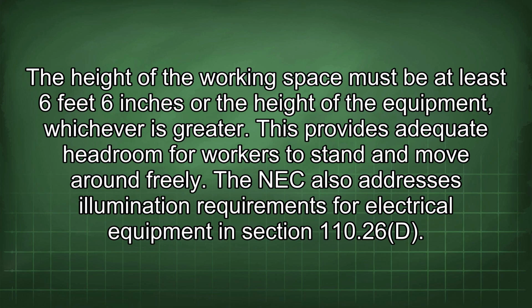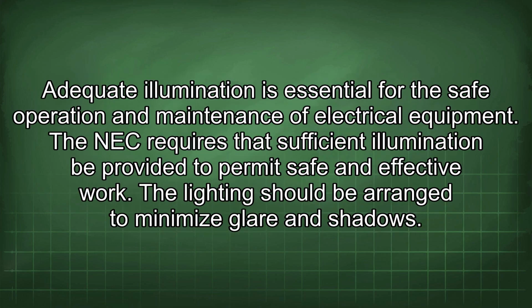The NEC also addresses illumination requirements for electrical equipment in Section 110.26(D). Adequate illumination is essential for the safe operation and maintenance of electrical equipment. The NEC requires that sufficient illumination be provided to permit safe and effective work. The lighting should be arranged to minimize glare and shadows.